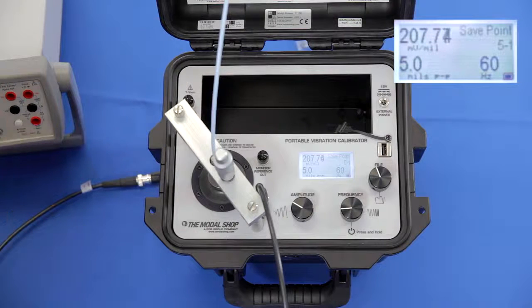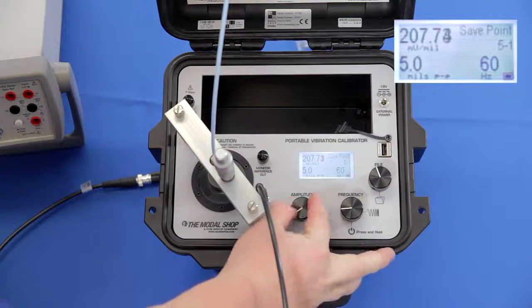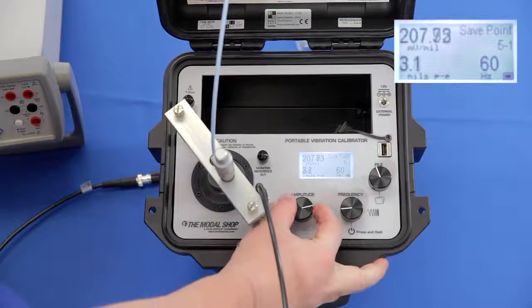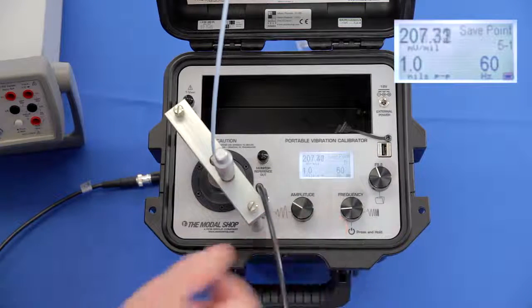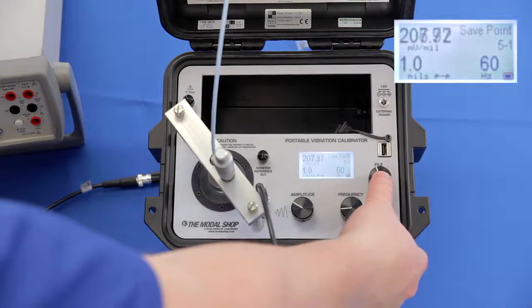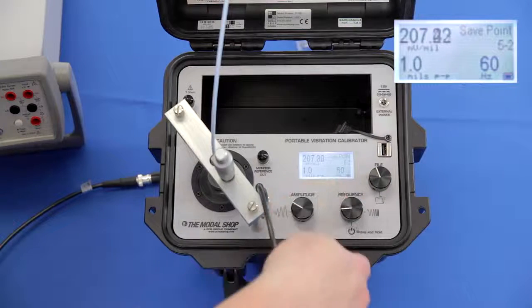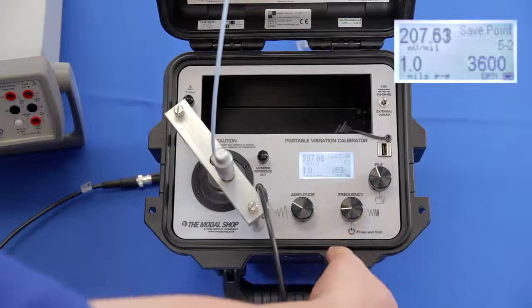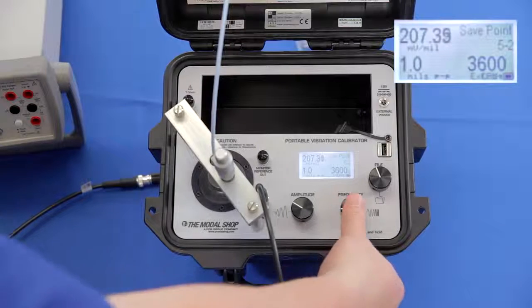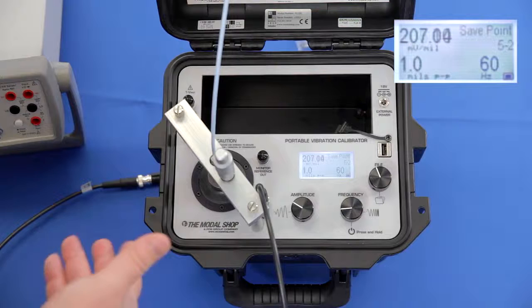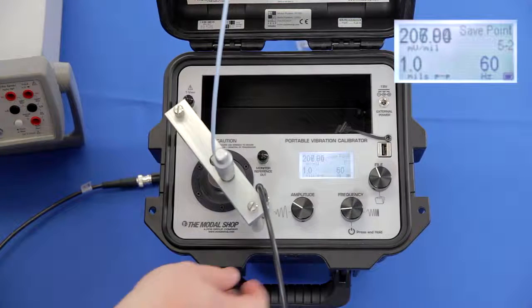So now let's create a calibration certificate for amplitude response for this proximity probe. I'm going to start all the way down at 1 mil peak to peak and save the point by pressing the file button. I'm doing this at 60 hertz, which is 3600 CPM. You can see I can toggle between hertz and cycles per minute by pressing the frequency button.